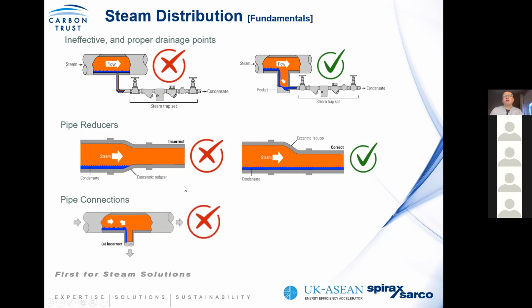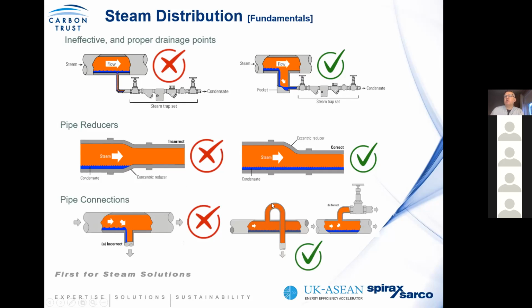And often we come across a scenario like this, where you would take a tapping to an end user, and basically you would drop from a vertical line down to the end user. In this scenario, however, the condensate in the distribution system will fall down into the end user, and you will find you could have a lot of water hammer problems, poor heat transfer efficiency, and very ineffective control. It's more beneficial that you take a tapping from the top of the distribution pipe. You should also look at an isolation valve as close to the tapping point as possible. And in doing so, you only take dry steam to your end user, eliminating problems with water hammer and poor heat transfer efficiency for that end user.